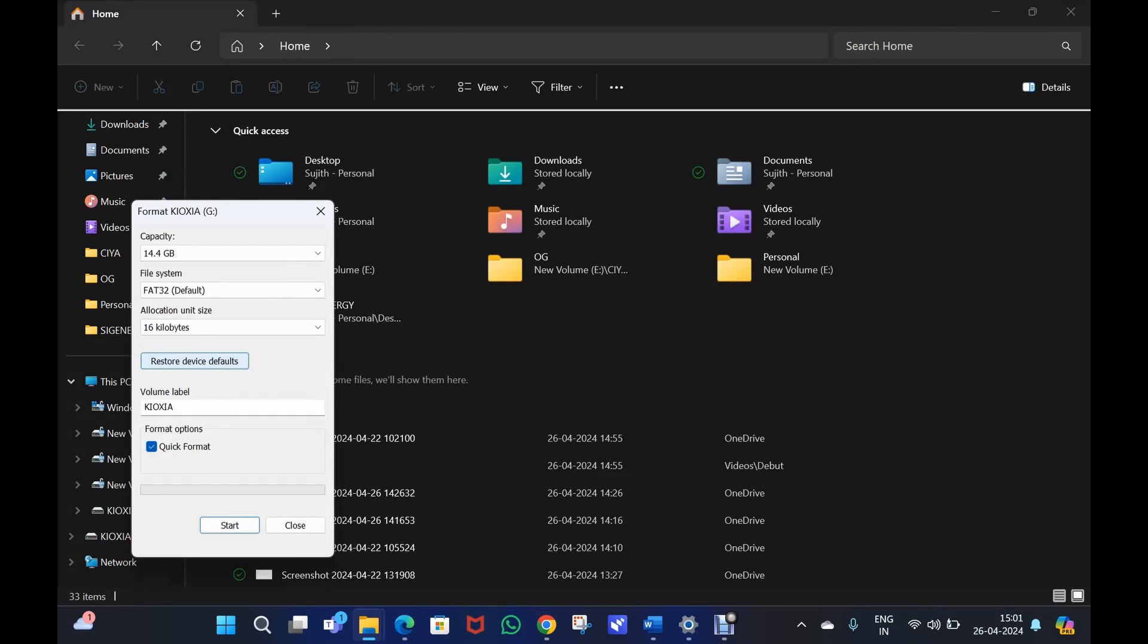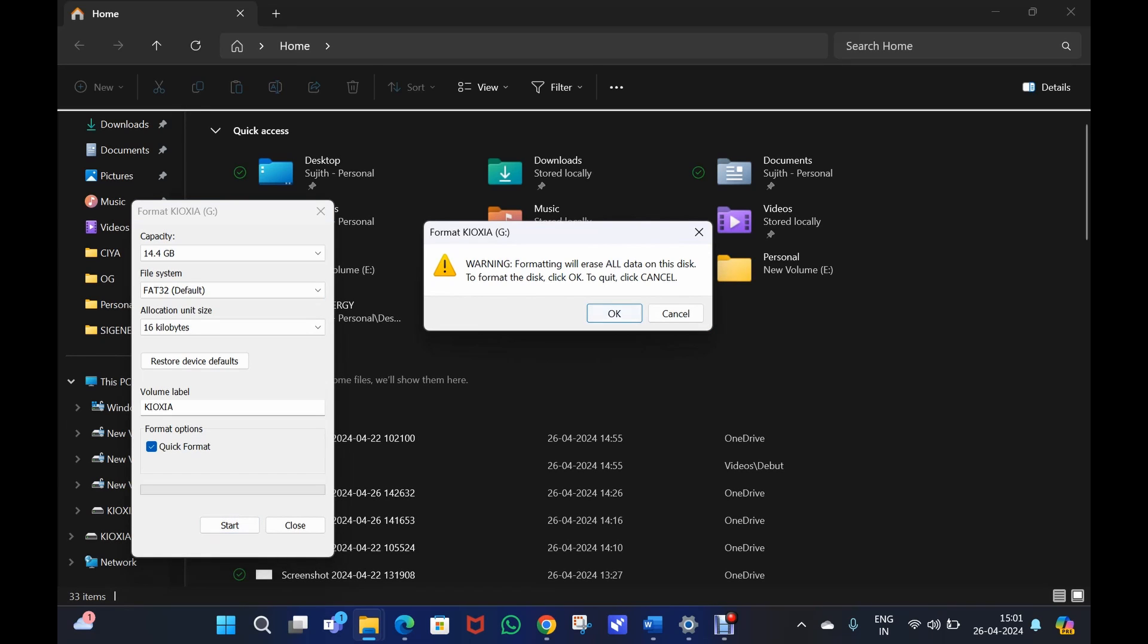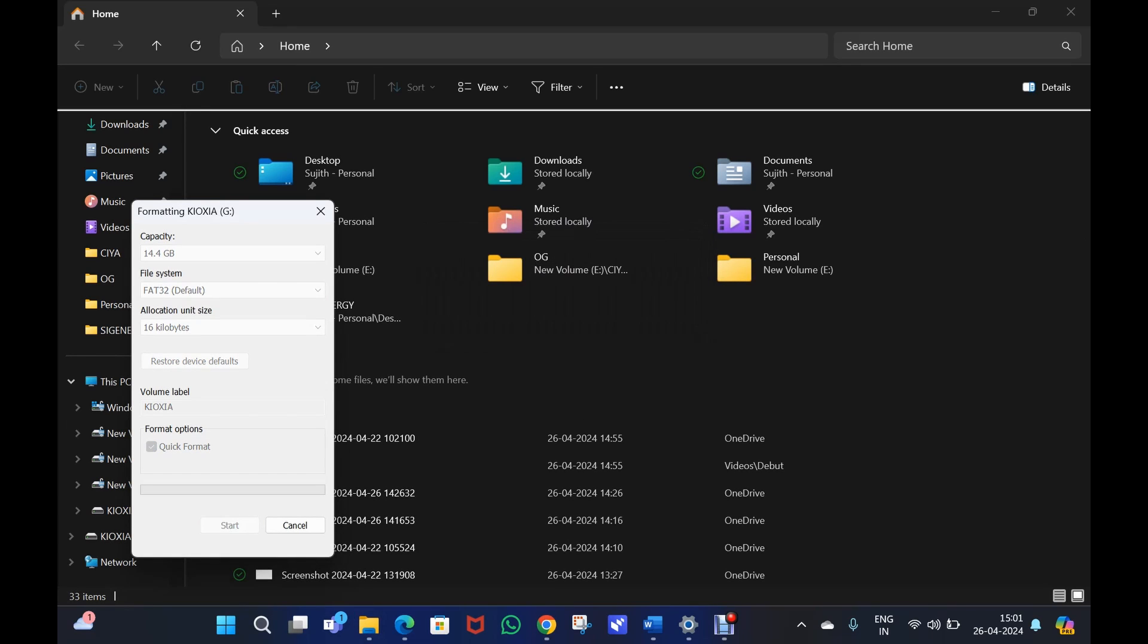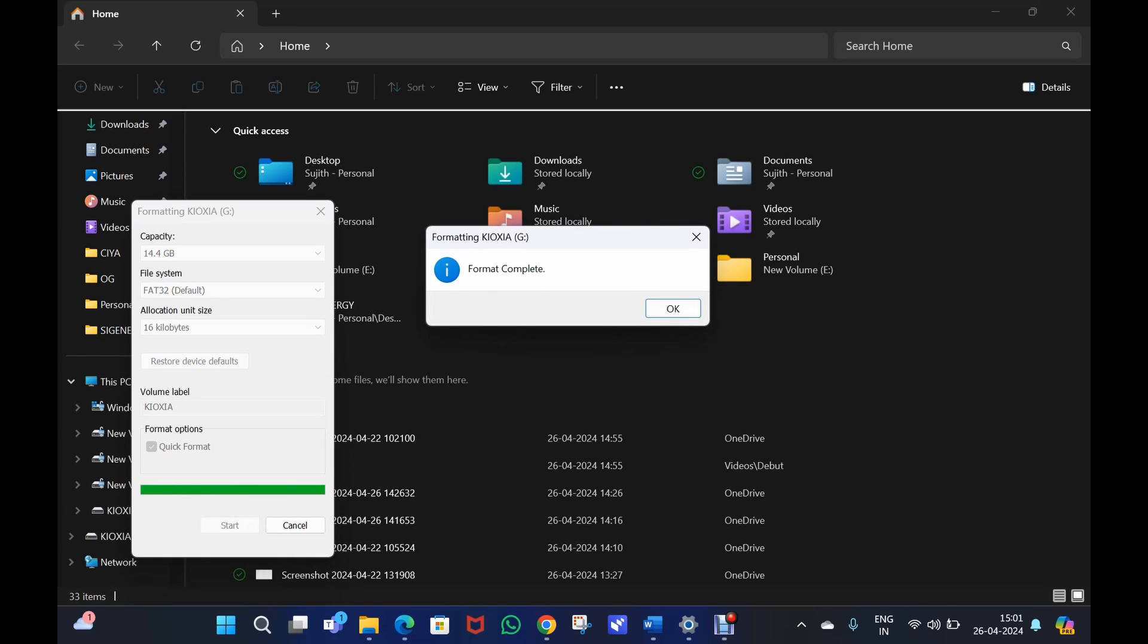Format the USB, so the file system needs to be FAT32. Otherwise the inverter won't see the USB. So when it starts we need to allow for the format. Format is complete.